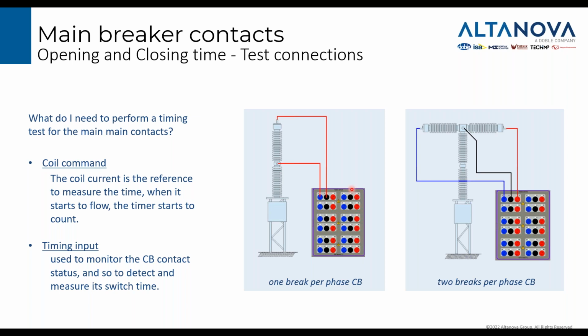With one break per phase, we connect just one input like this. If I have 2 breaks per phase, I have a common point in the middle here, and the first break and the second break. This connection must be repeated for all 3 phases. In this representation, we have only one for simplicity.